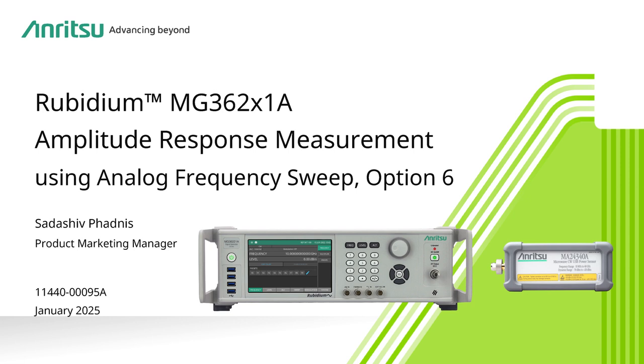Rubidium's analog sweep capability, along with sweep synchronization outputs generated, can be used to make amplitude response measurements of active and passive devices. This video will discuss in detail how to set up and measure the amplitude response of a bandpass filter centered around 1.85 GHz with a 200 MHz passband.